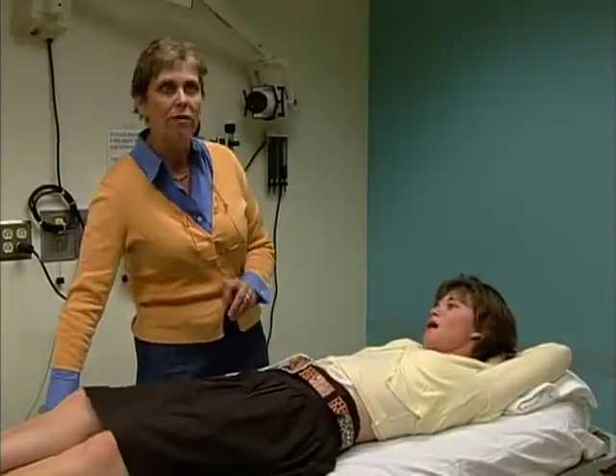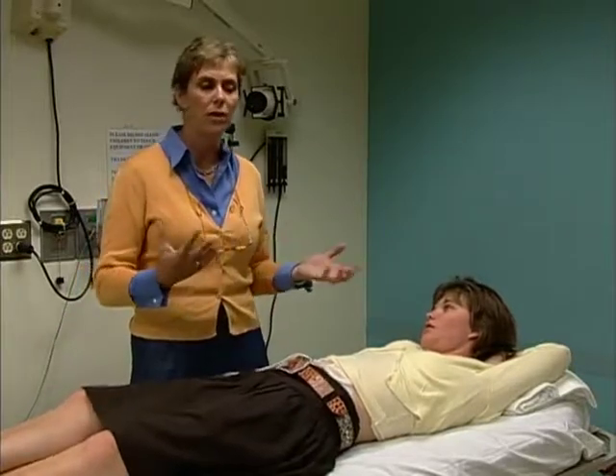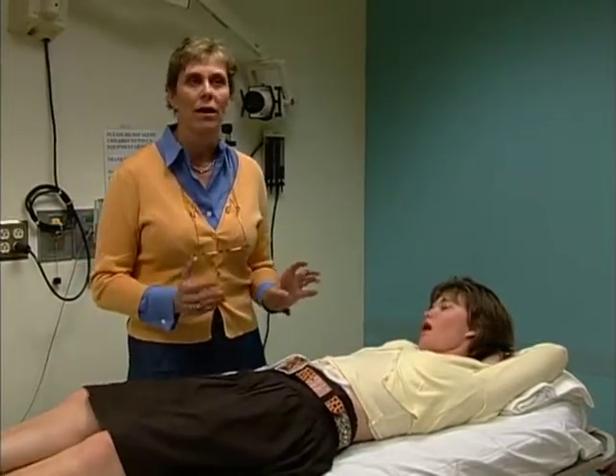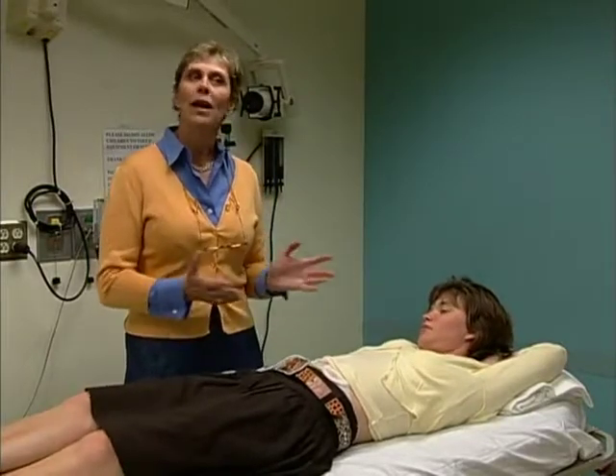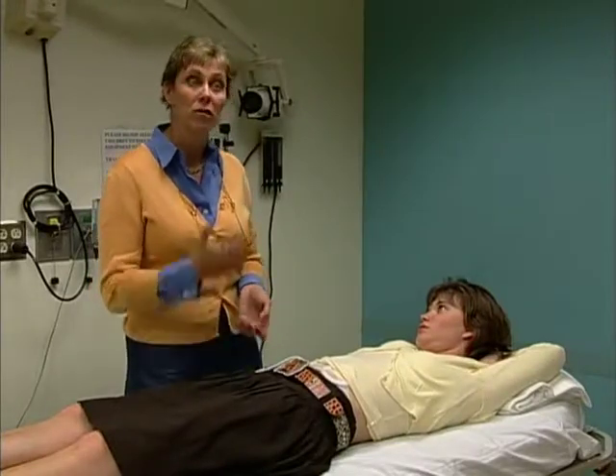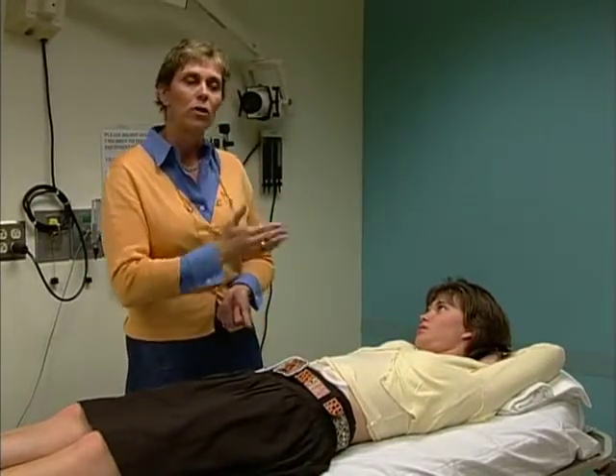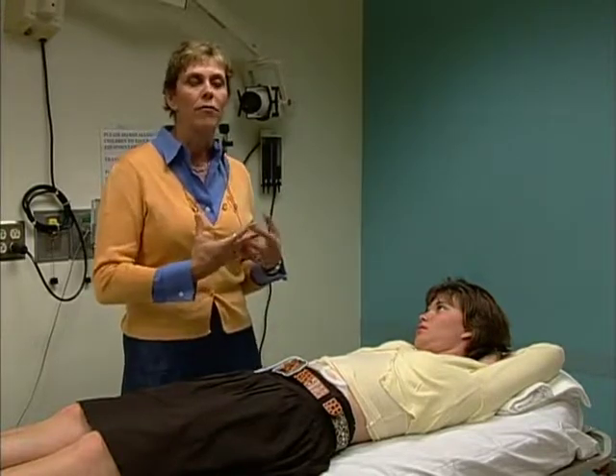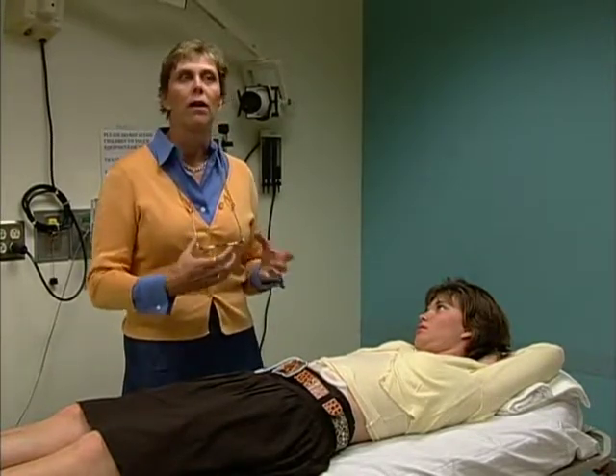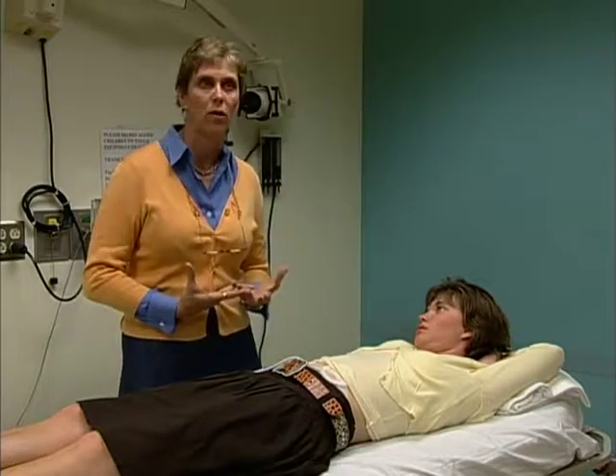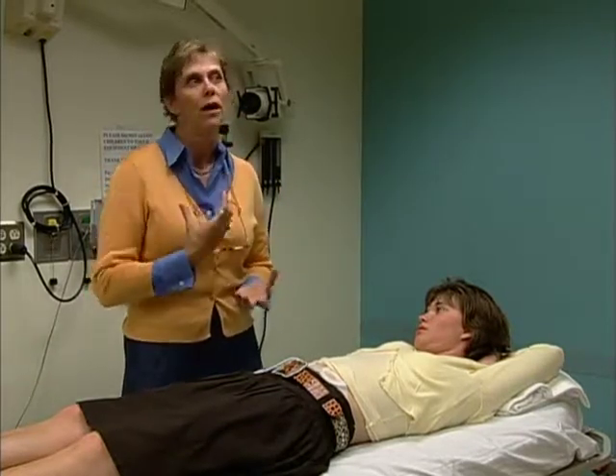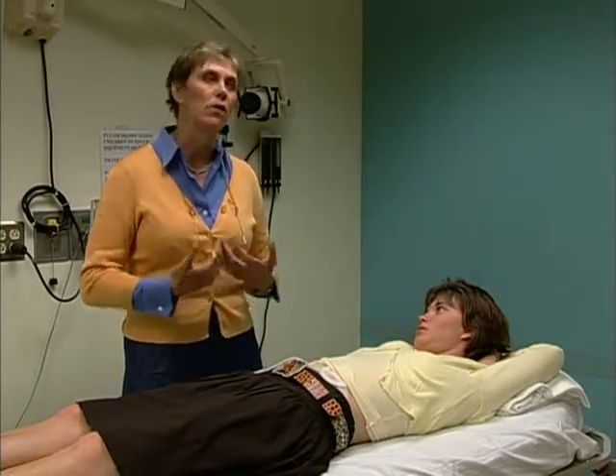Sometimes there are problems with diaphragm pacing that require adjustments to the equipment. One involves sensitivity to the equipment settings. When we started using the machine as Avery sent it from their factory, we determined an amplitude of, say, 3.1. At 3.1, that amplitude was not strong enough to create inhalation. And yet when you move to 3.2, which is the next notch up on the dial, you contract so hard that the diaphragm is so stimulated that the force just pulls down the airway, and so you have an obstructed airway. Bottom line is you don't have air coming in, you don't have a breath.